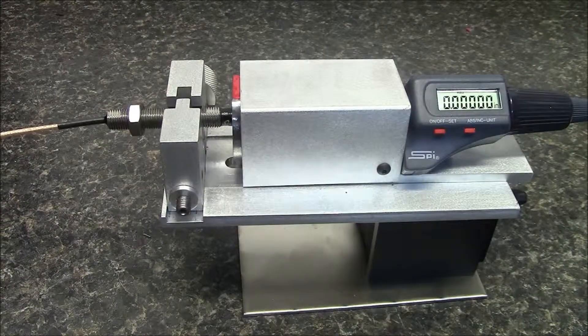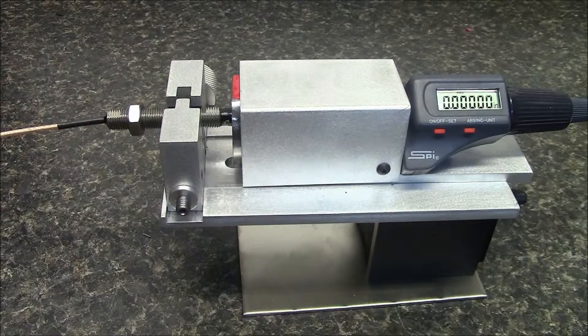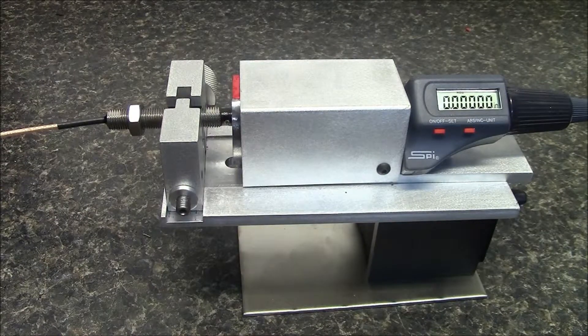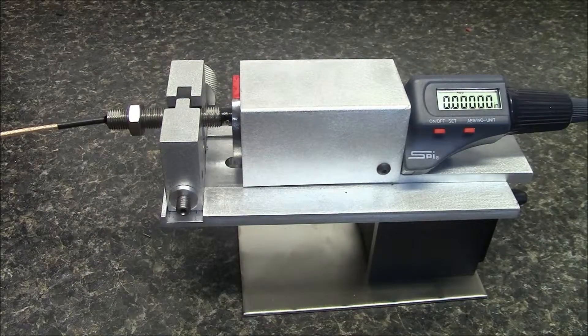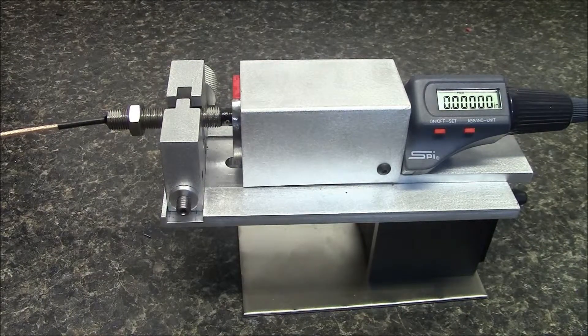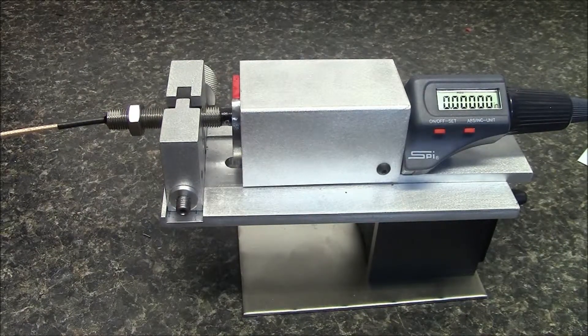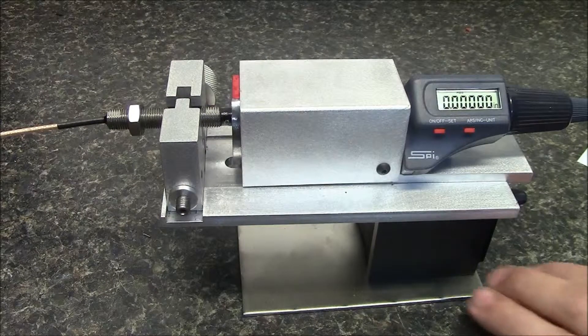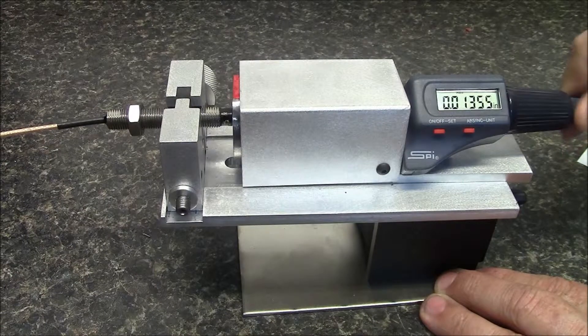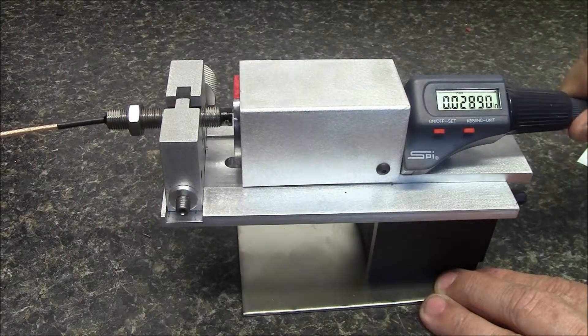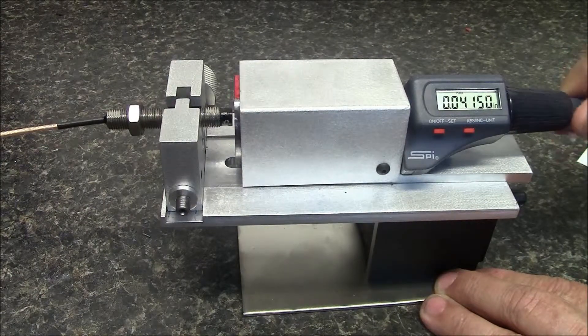Mechanical run-out is caused by the surface of the target material not staying perfectly parallel to the surface of the eddy probe throughout the entire measurement process. By mounting the target material on linear bearings, we keep the surface of the target material and eddy probe perfectly parallel throughout the entire measurement process.